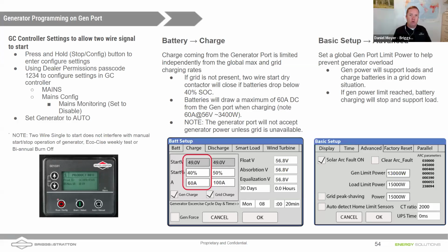But if you backed up the whole home, the generator is going to see grid even when you lose grid, because you're now using energy from a battery and solar to power the home. You've got to get into the controller on the generator and tell it to disable mains monitoring, or say that if you still see the presence of grid, which it isn't grid, right? It's the grid being formed by the Sol-Ark, but you see the presence of the two-wire signal to start, go ahead and start up. So that's what I'm talking about on the left.